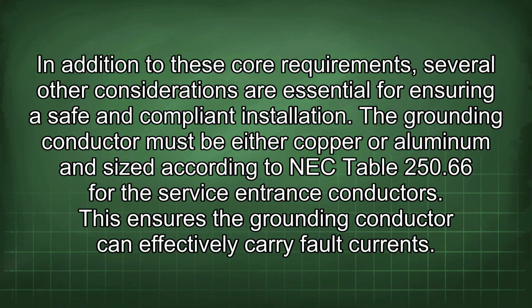In addition to these core requirements, several other considerations are essential for ensuring a safe and compliant installation. The grounding conductor must be either copper or aluminum and sized according to NEC Table 250.66 for the service entrance conductors. This ensures the grounding conductor can effectively carry fault currents.